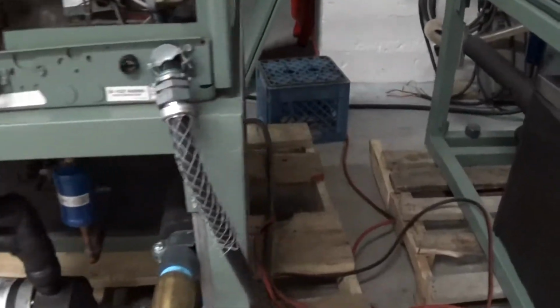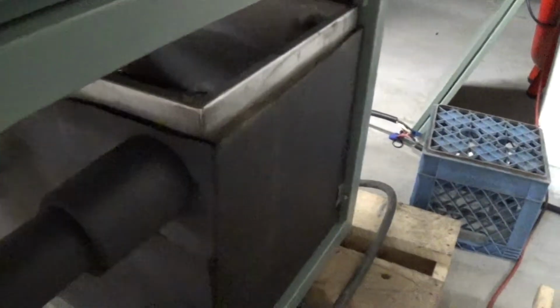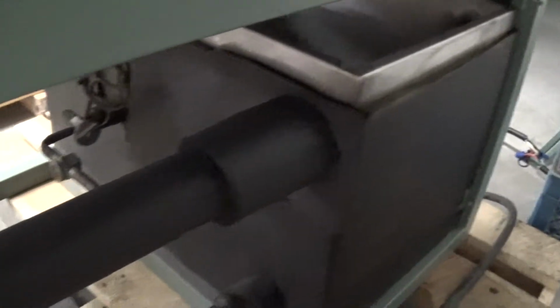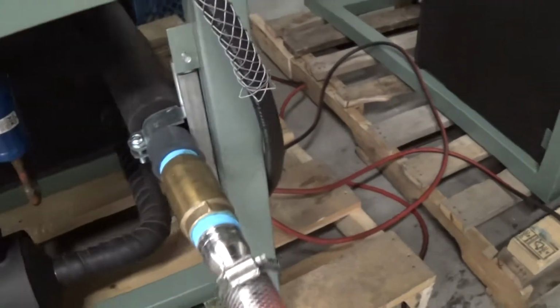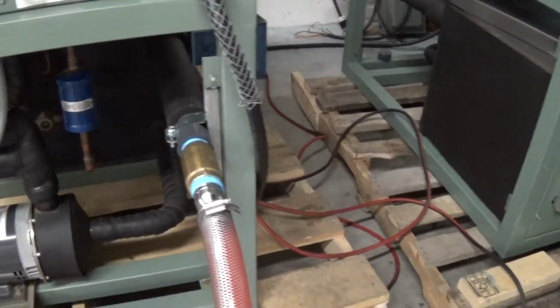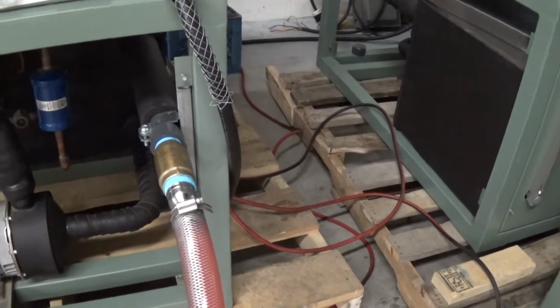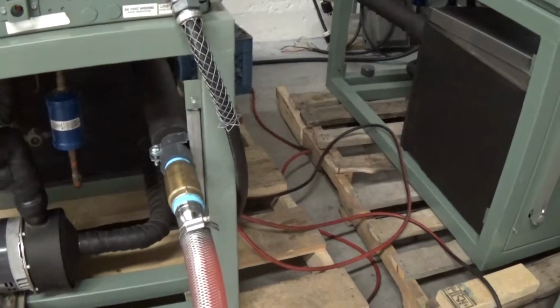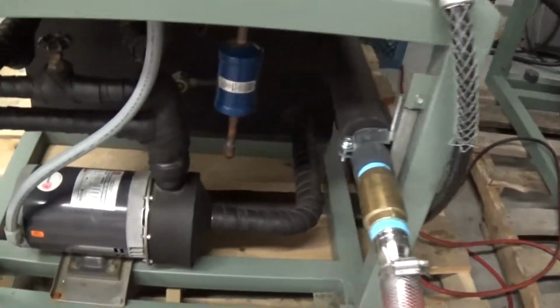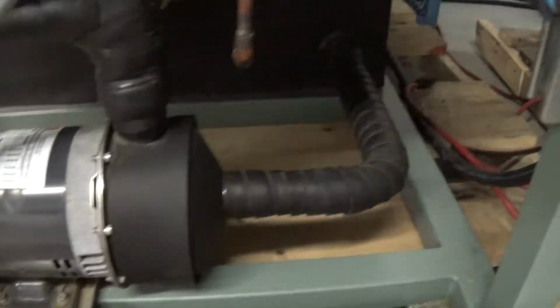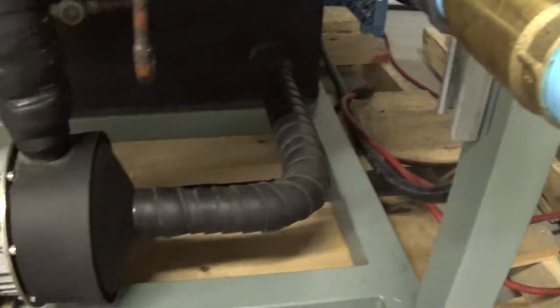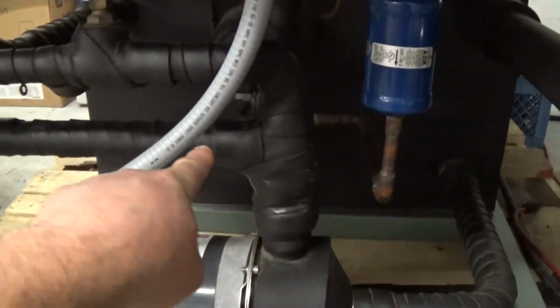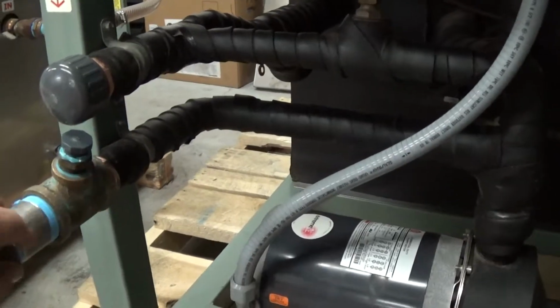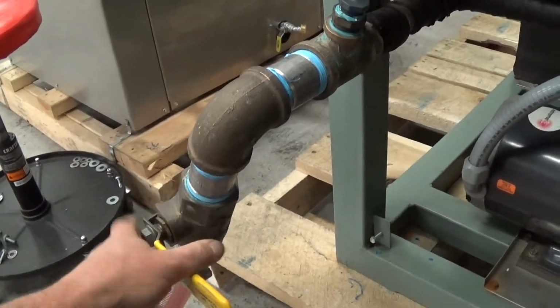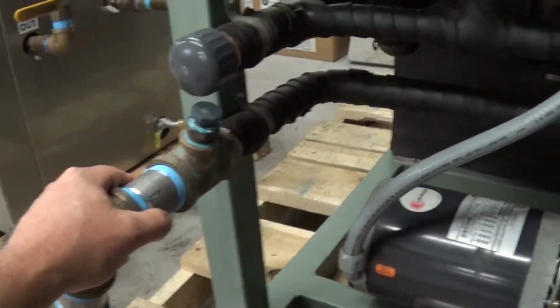So we actually, here at KIG, punch a hole in the stainless steel tank, and we have this new line that comes out here. Okay, and this is your return. That's a zero pressure return, so there's no pressure required coming back to the unit, which is what you want for a brewery application. So the pump draws off your tank here and comes up here. This line here, the bottom one, comes out to your process. That comes out to your supply for your brewery tanks.